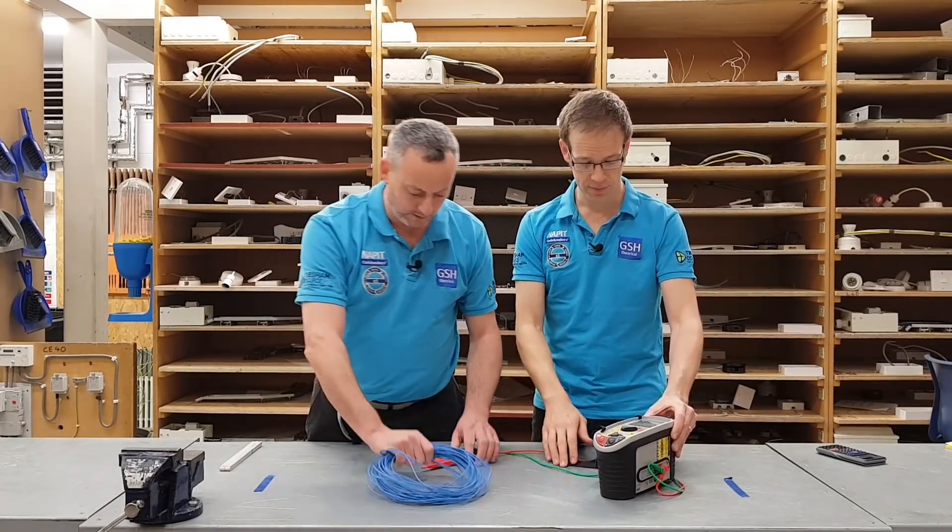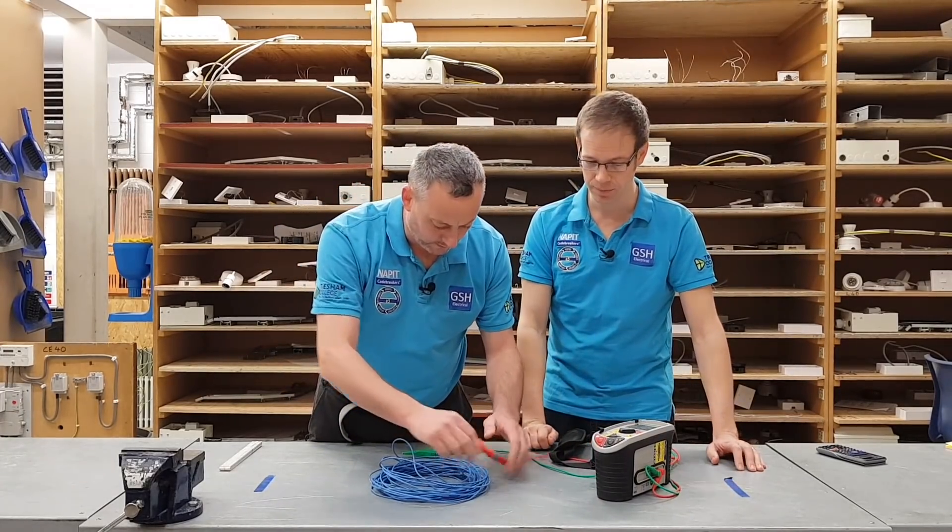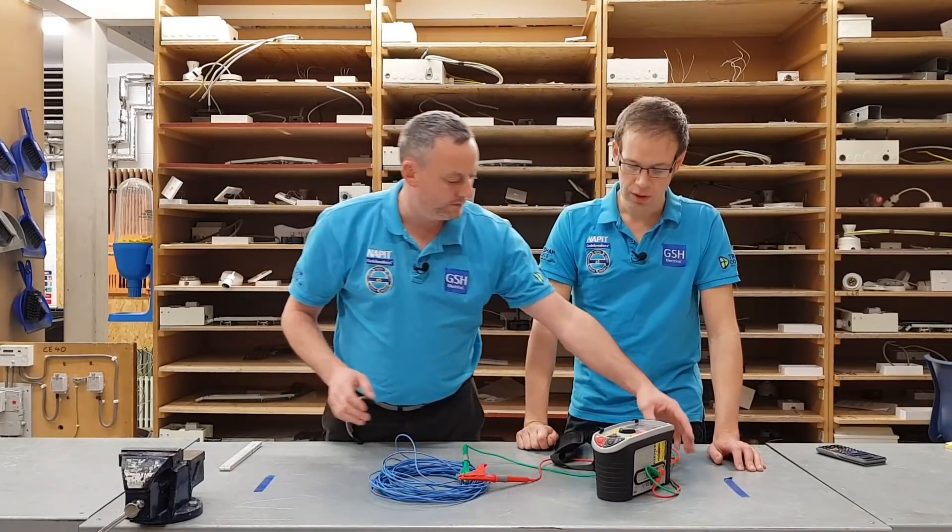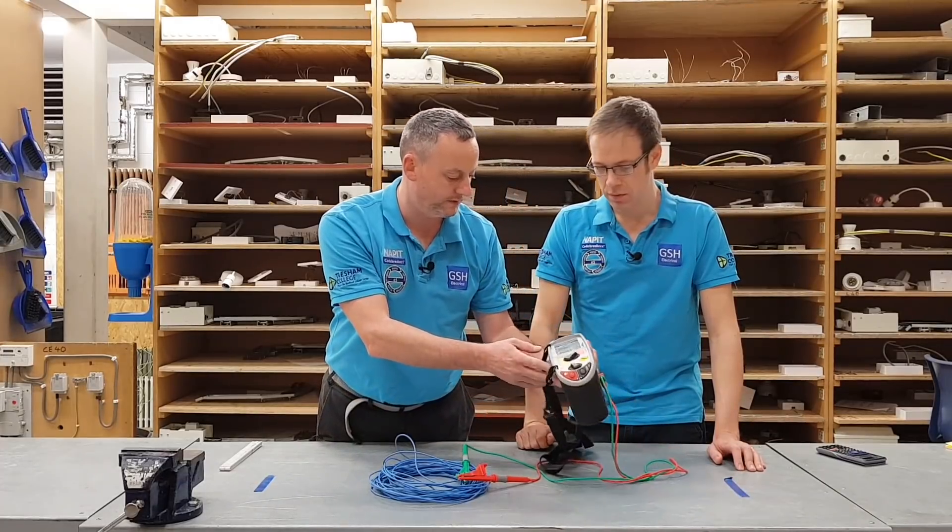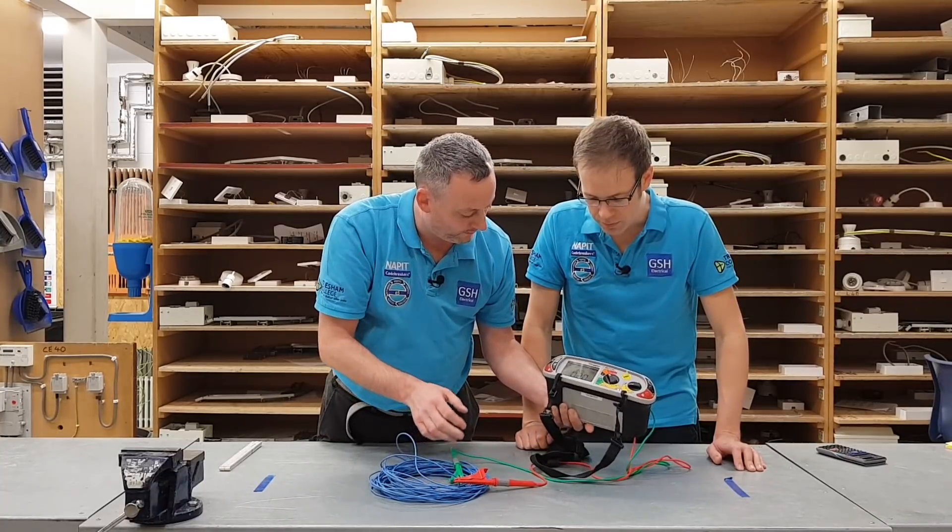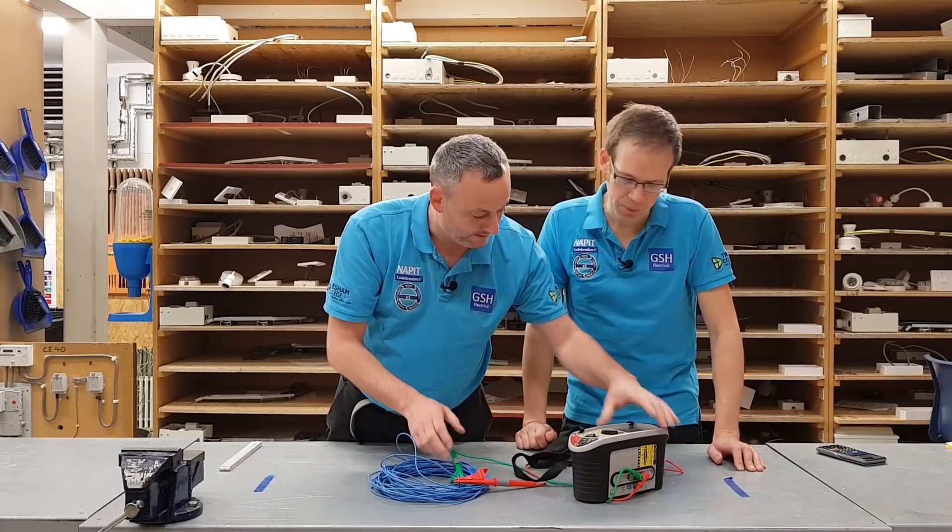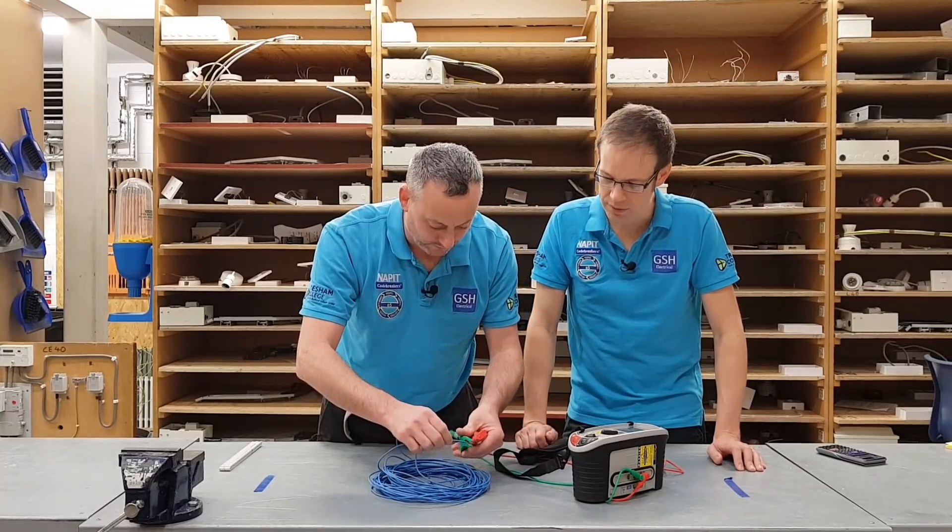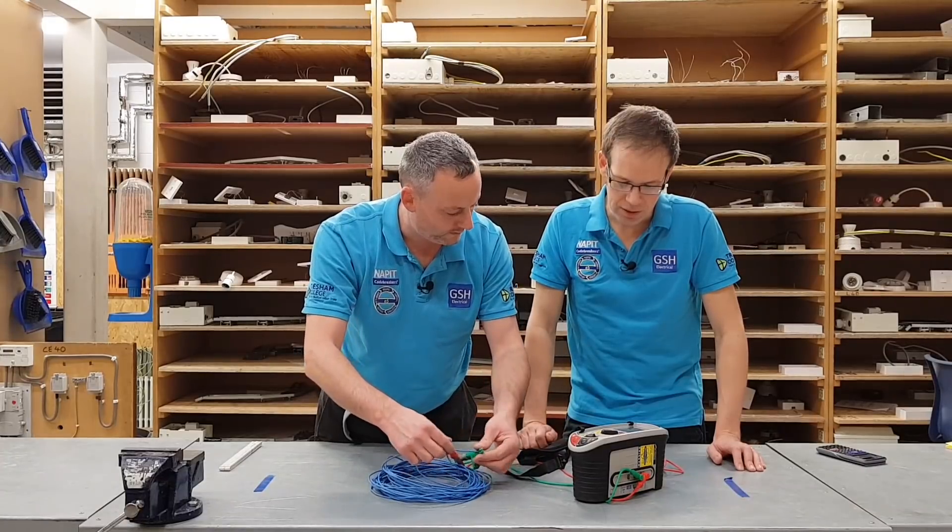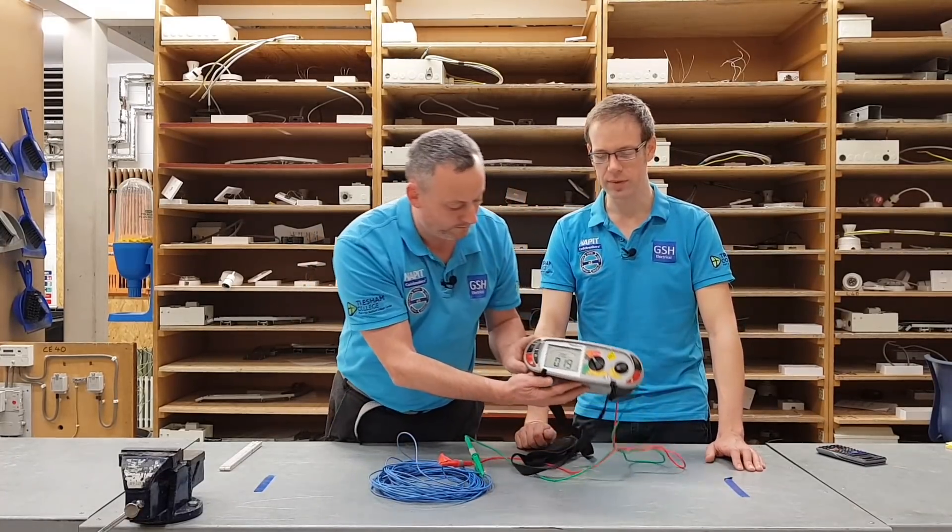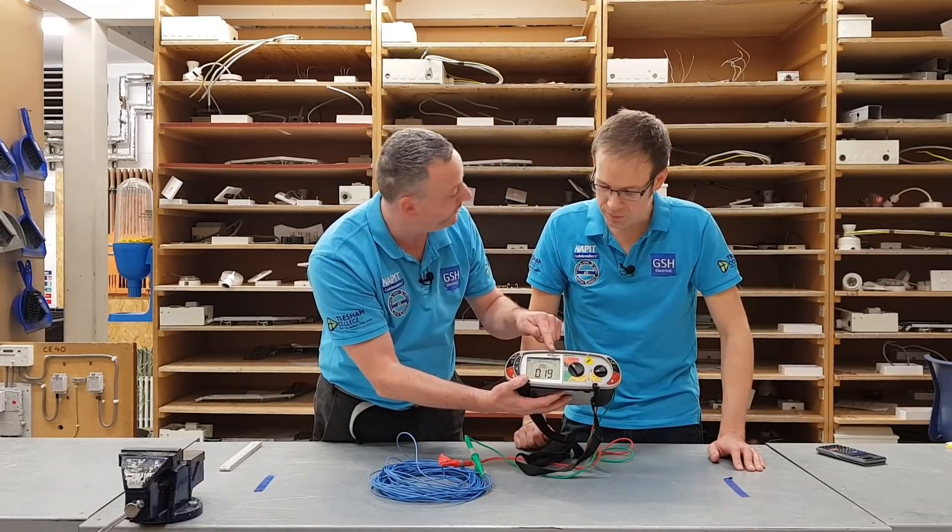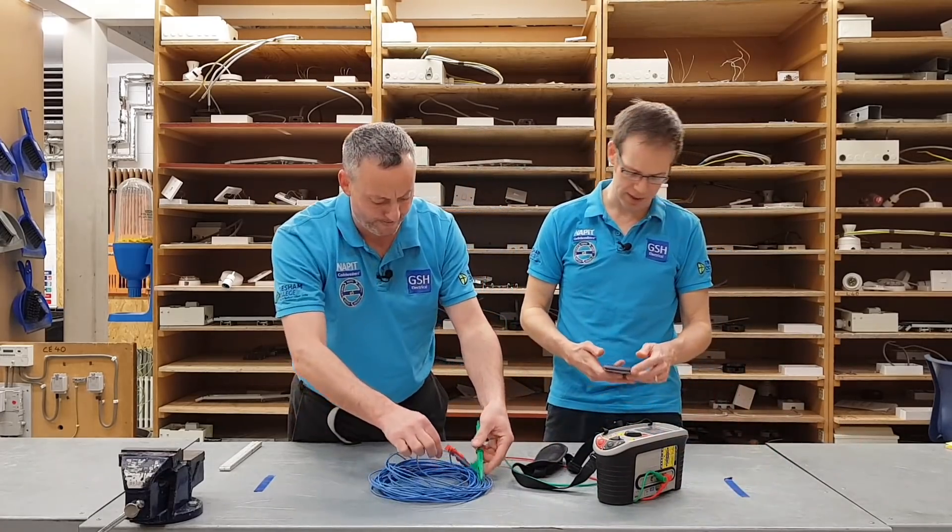If I use this? Yeah, I've got my MFT ready to go. Let's work out the resistance of this. And we have got fluctuating between 1.8... Oh it keeps, you knocked it again. So let's just give this a little squeeze between 1.8 and 1.0. It's gone between 0.18 and 0.2, so shall we go with 0.19? So it's coming out at 0.19 of an ohm after I've fudged around with it there and knocked it over and all the rest of it. So we are at 0.19 of an ohm.